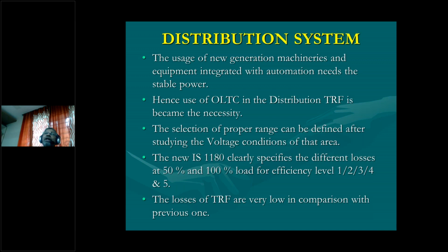In my existing projects, I can give some examples, projects which I did more than 25 years ago. Now we tried to work out the current losses of those older transformers, which have been working in the system for more than 25 years. If you replace the transformer by IS 1180, the payback comes in 2.5 years. Of course, it's meant for continuous industry, a continuous process running around the clock. But these are the results of the new IS. So let us move to the next slide.